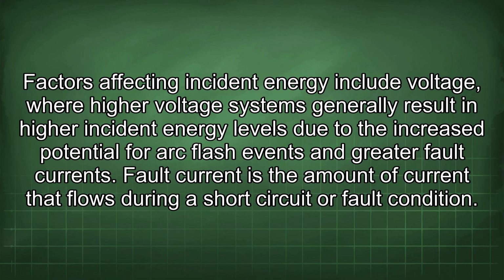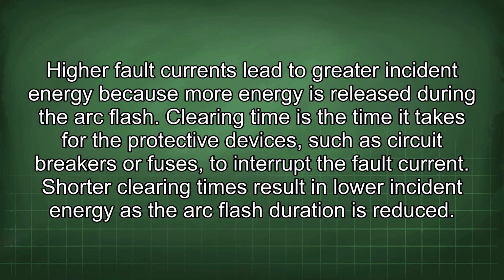Fault current is the amount of current that flows during a short circuit or fault condition. High fault currents lead to greater incident energy because more energy is released during the arc flash. Clearing time is the time it takes for the protective devices, such as circuit breakers or fuses, to interrupt the fault current. Shorter clearing times result in lower incident energy as the arc flash duration is reduced.